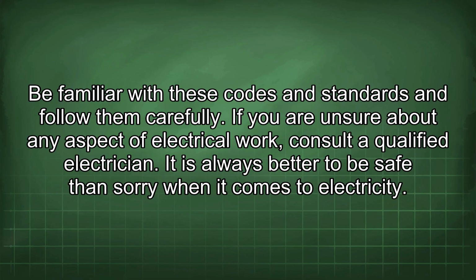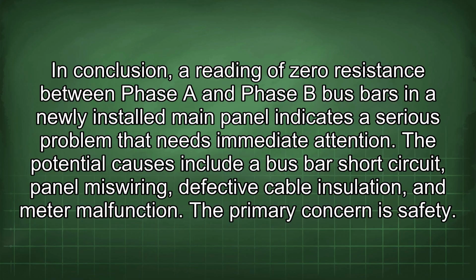If you are unsure about any aspect of electrical work, consult a qualified electrician. It is always better to be safe than sorry when it comes to electricity. In conclusion, a reading of zero resistance between phase A and phase B bus bars in a newly installed main panel indicates a serious problem that needs immediate attention. The potential causes include a bus bar short circuit, panel miswiring, defective cable insulation, and meter malfunction.